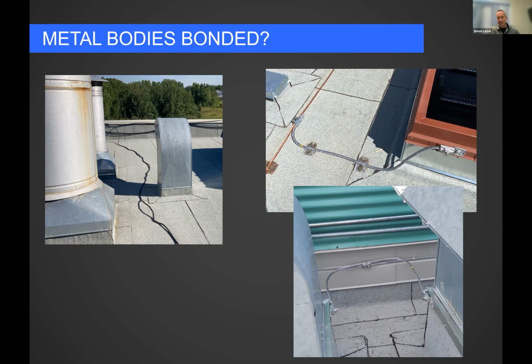And again, 2 meters, if they're within 2 meters and they're bonded, good. If something's 2.5 meters away, probably doesn't need bonded. And one thing you will occasionally see is we sometimes go overboard on our bonding. We'll bond to rooftop drain covers. Are those grounded? Maybe, but we bond to them anyway if we go right by just to cover all our bases, even though we know that underneath the stormwater drains are jointed with rubber insulators and stuff like that. That's not a continuous path to ground necessarily. We'll still bond it occasionally just to make sure there's no question.